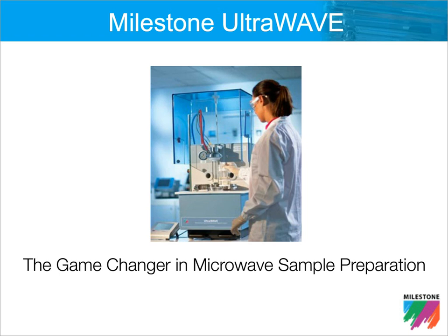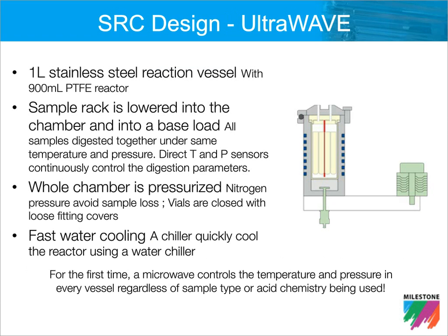And you also have a fair amount of cleaning that needs to take place because you have to clean those Teflon or quartz components in between runs. Finally, because we are doing digestions inside polymer type materials, fluoropolymers, we still do have limitations in terms of the temperatures and pressures that can be achieved.